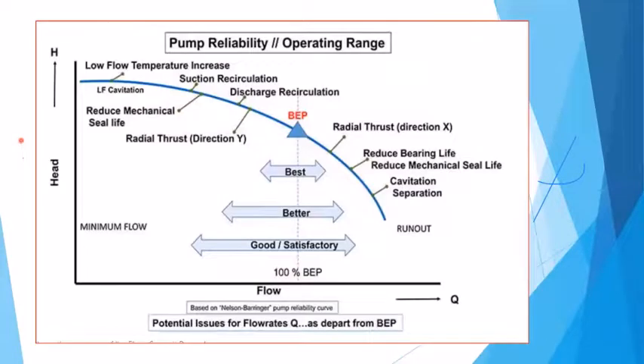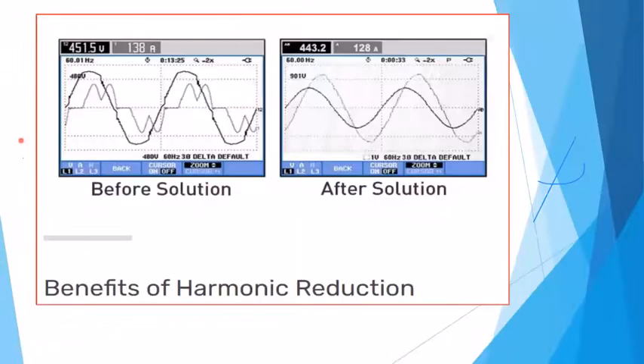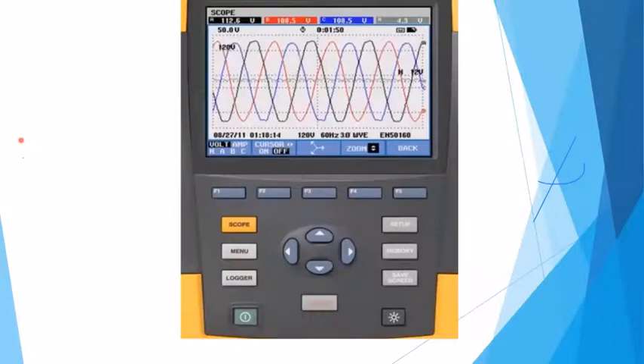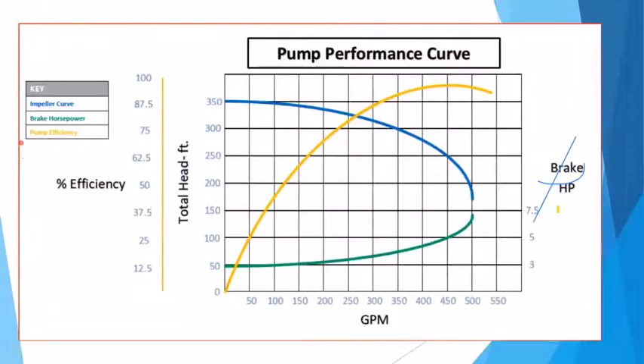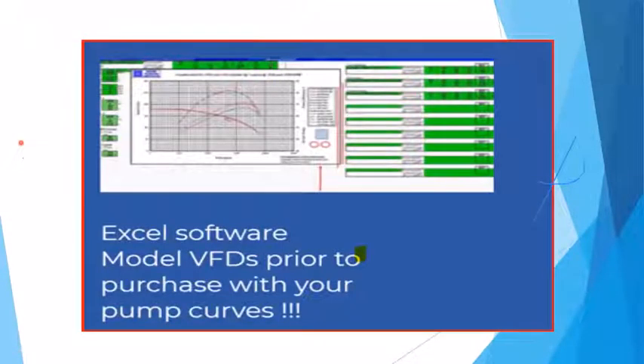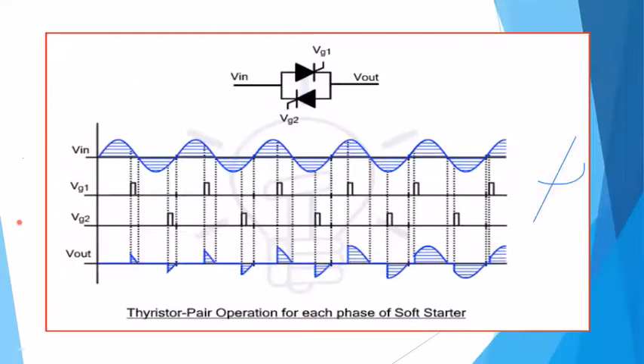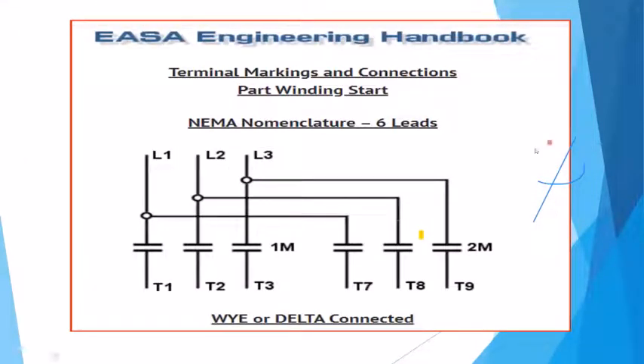This is where I feel, if you talk to the power company and you just simply need 2 starter contacts, you can get by with the soft starting way of part winding. And so basically just bring in this contact. It's the old contactors. There's nothing to wear out other than the contacts over time, but I've seen these things 30 years old and still working.